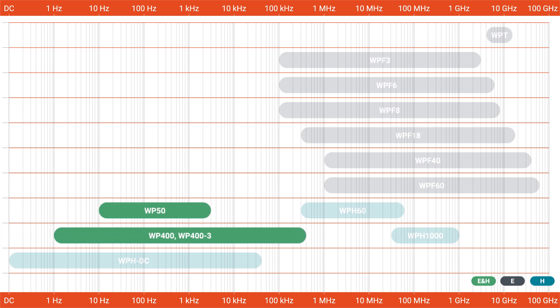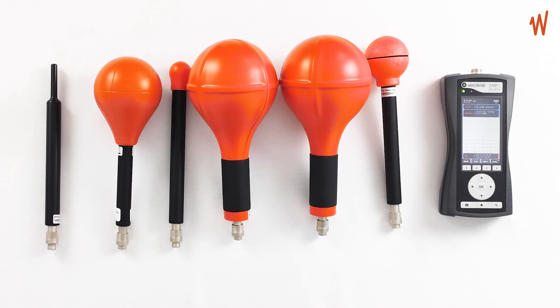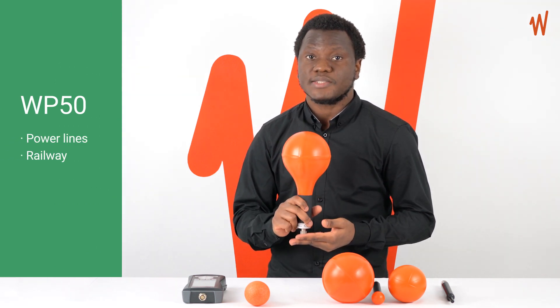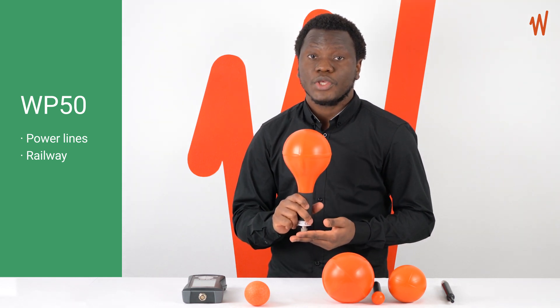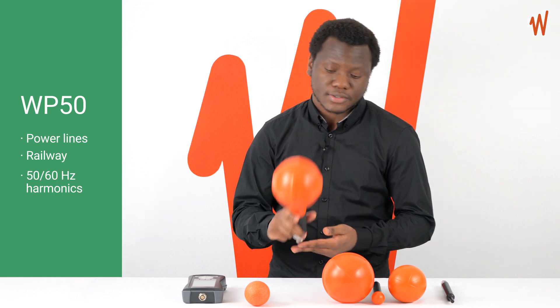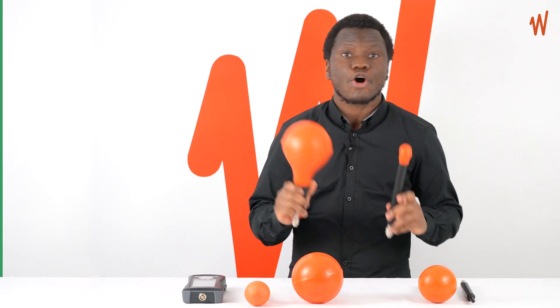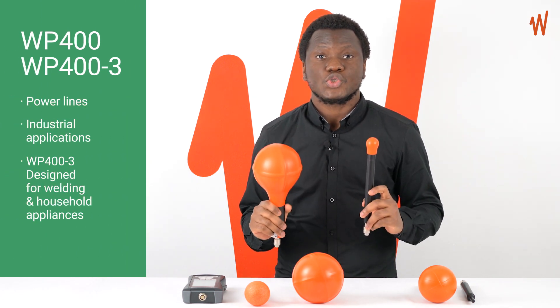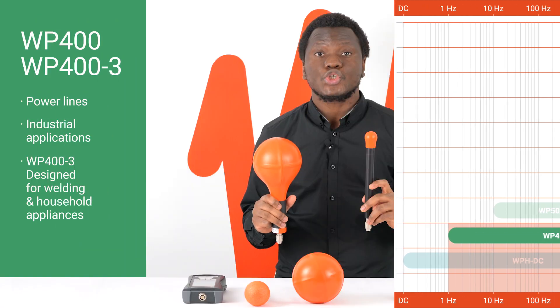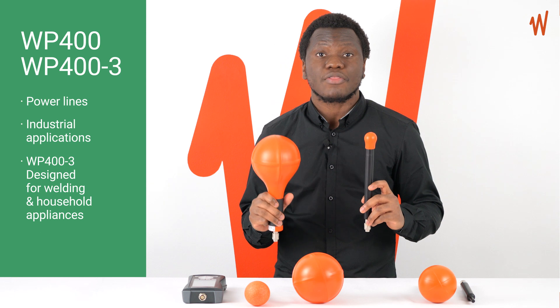In the low frequencies, it's common to find yourself in near-field conditions. In this case, you would need to measure both electric and magnetic fields. So we've designed the WP series probe to measure both electric and magnetic fields with the same probe. The first is the WP50 probe, which is specially designed to cover power line frequency measurements and similar applications like railway. This probe covers from 10 hertz up to 3 kilohertz to cover the 50 or 60 hertz harmonics. The second type is the WP400 and WP400-3, which also measure both electric and magnetic fields, covering from 1 hertz up to 400 kilohertz for power line frequencies and many other industrial applications.